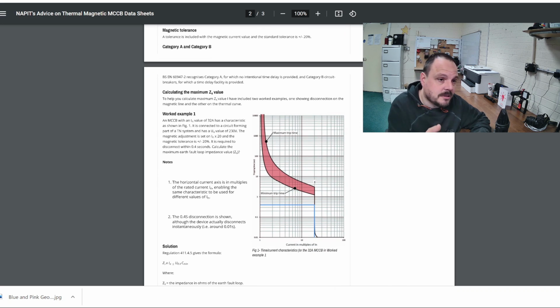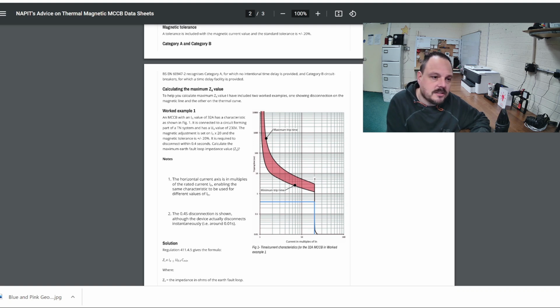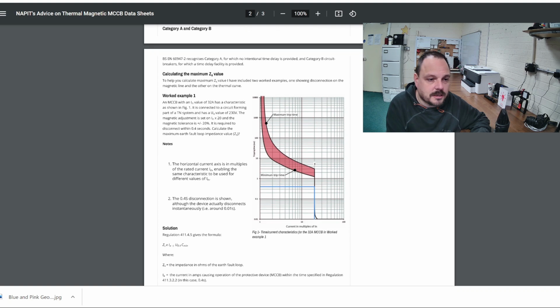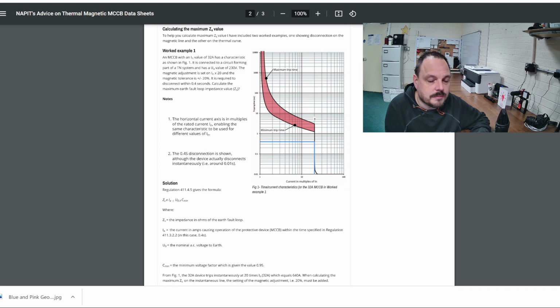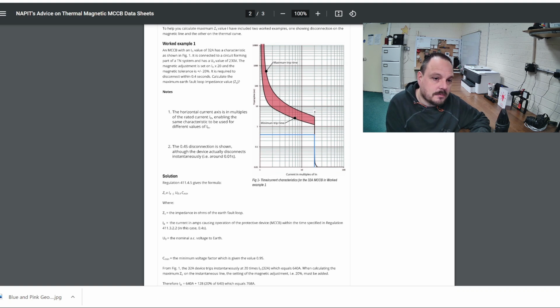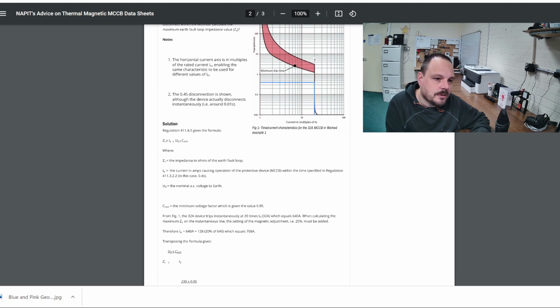Basically you would do that as it explains here, so it's using an MCCB rating of 32 amps. It's looking at the Uo value of 230 volts. The magnetic adjustment is set to times 20, and the magnetic tolerance is plus or minus 20%. So it's required to disconnect within 0.4 seconds, calculating earth loop impedance value maximum for that particular product. It shows you on the graph, which should look familiar from the wiring regs. And it says here the 0.4 second disconnection is shown, although the device actually disconnects instantaneously, i.e. around 0.01 seconds. So they've marked that, plotted it on the graph. And it shows you here how to work that out using regulation 411.4.3, and again that's perhaps changed because this will be based on an older version of the regulations.